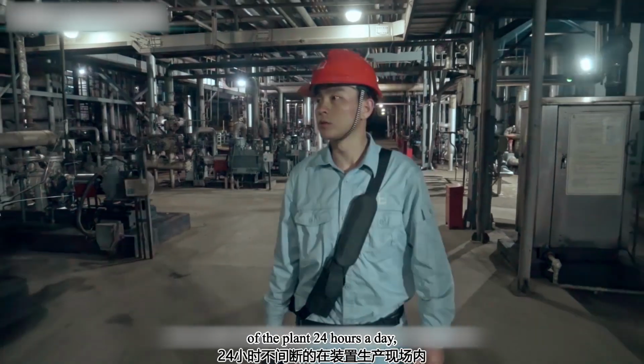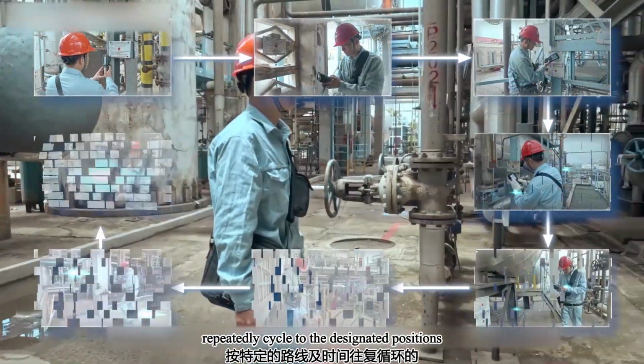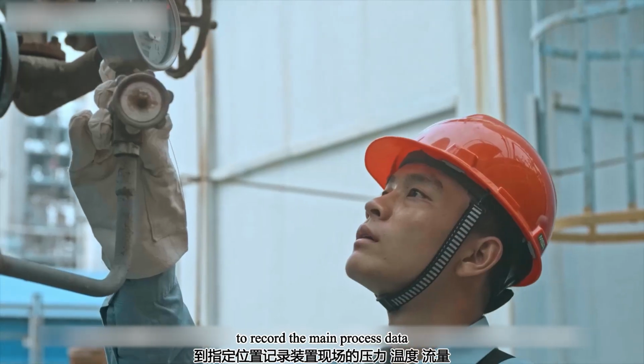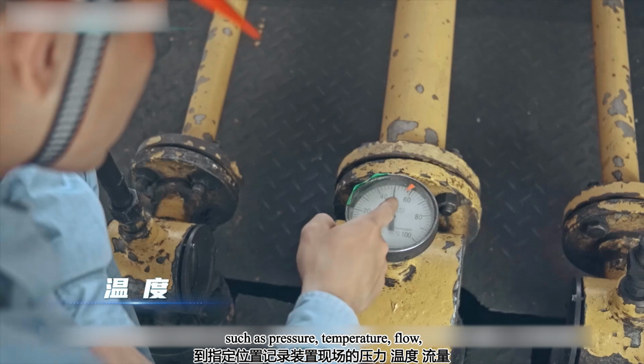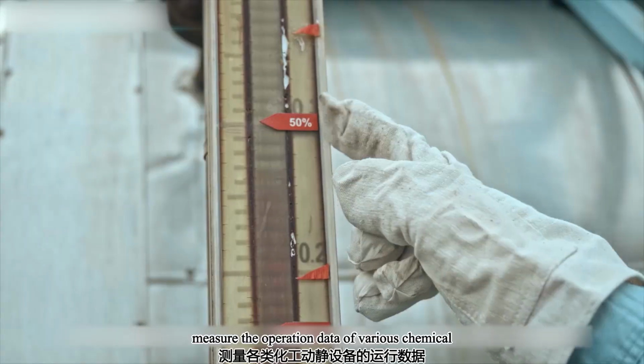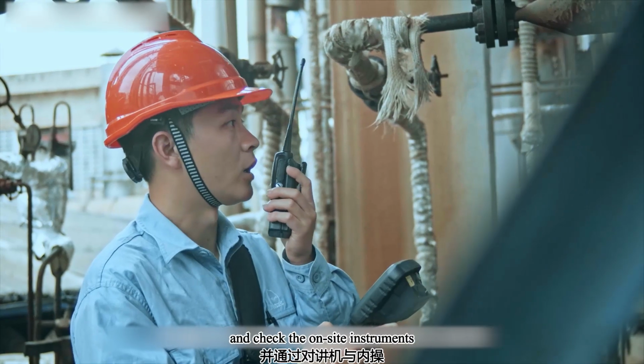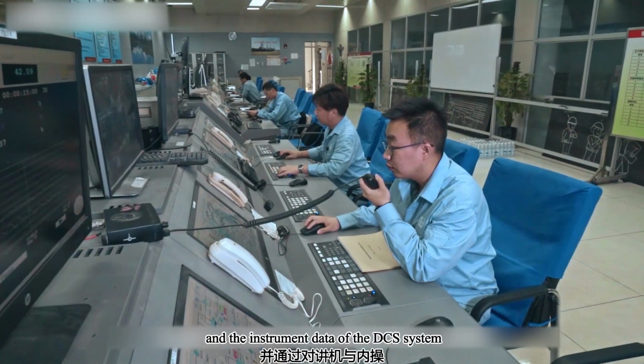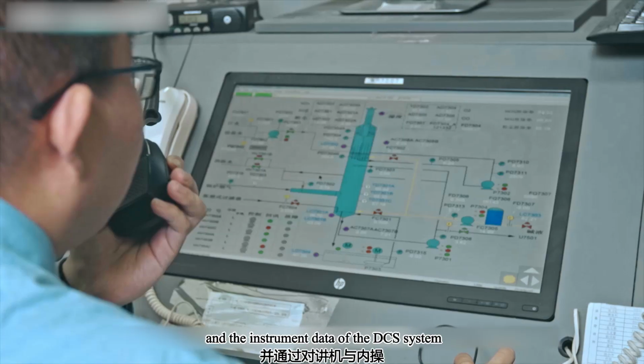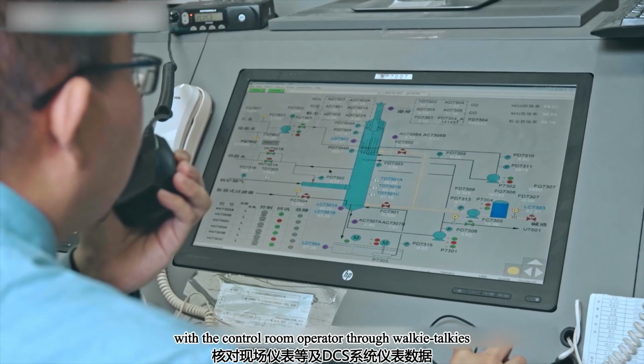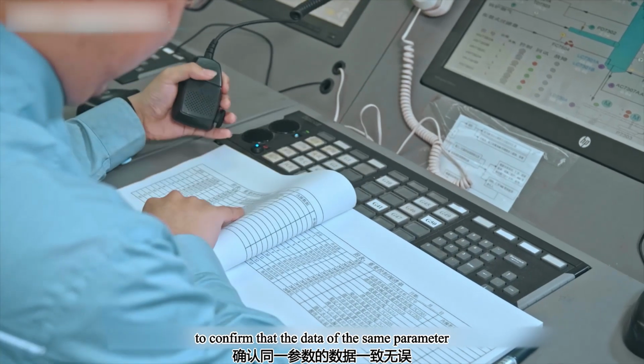They continuously patrol the production site of the plant 24 hours a day, repeatedly cycling to the designated positions according to a specific route and time, to record the main process data such as pressure, temperature, flow, and liquid level at the plant site, measure the operation data of various chemical static and dynamic equipment, and check the on-site instruments and the instrument data of the DCS system with the control room operator through walkie-talkies to confirm that the data of the same parameter are consistent and correct.